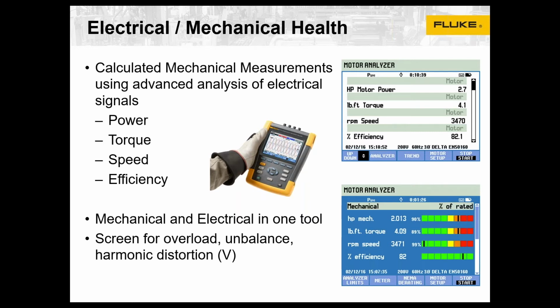The lower screen there actually shows a dashboard format where you can feed NEMA nameplate information into the motor analysis portion of the tester, and then you can determine: am I running this motor in an overload condition? And then that might point you to further diagnostics in the drivetrain. Why do we have that overload occurring? So that might be something, again, to ensure motor health, to make periodic measurements through the electrical connection to be able to look at and assess mechanical performance as well.